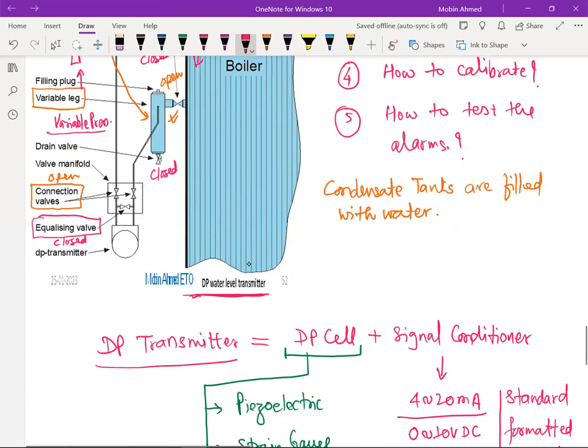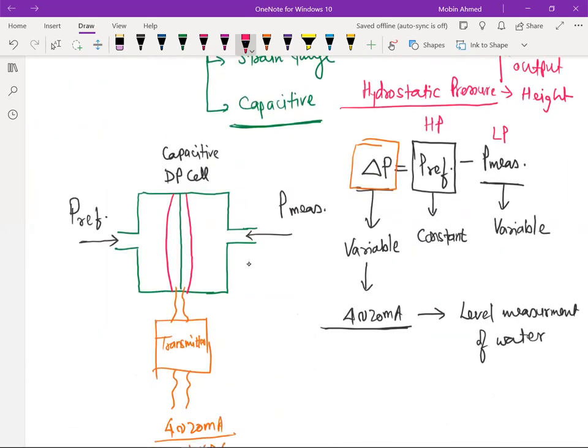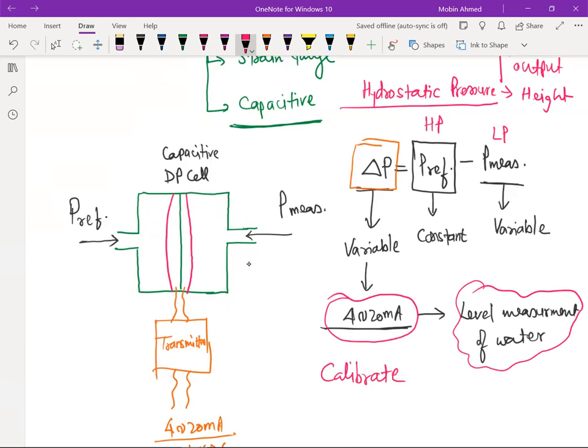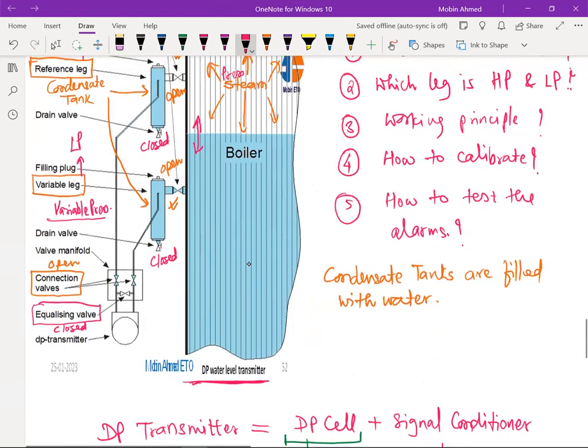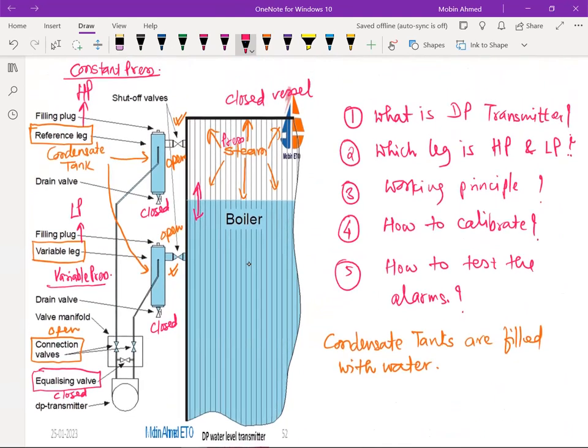Now we can have an output here. So this is the output. We are going to get a differential pressure output, differential meaning difference. That's why we are getting this output of 4 to 20 milliampere, which is going to give a level measurement of the water. Now we need to calibrate this to get 4 to 20 milliampere. So how are we going to calibrate this? During commissioning, or whenever we change the DP transmitter, we need to calibrate this. Okay, so how are we calibrating? Let's see about this one.